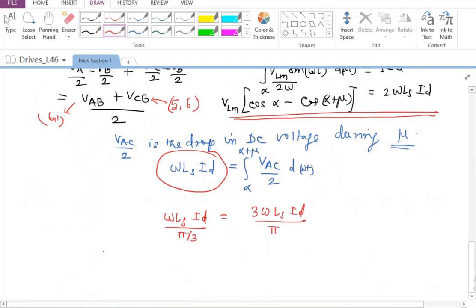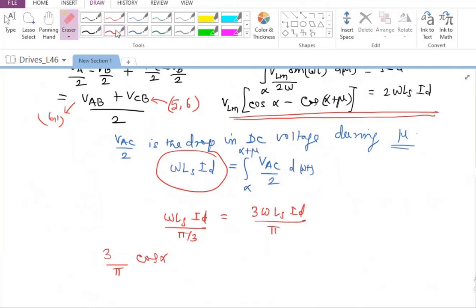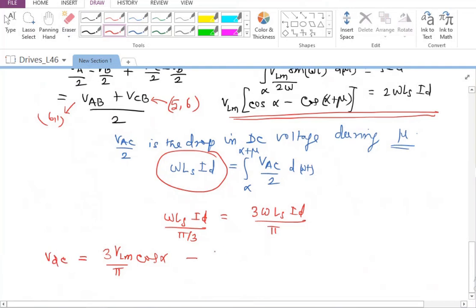So normally if we write 3 Vm divided by pi cos alpha, where Vm is the line voltage peak. Let me write this as VLM divided by pi cos alpha as the DC link voltage. Now from this I have to subtract 3 omega LS ID divided by pi, and that is going to be the DC link voltage. And if already this is negative, this will be adding to the total negative value. So the negative value would have increased as far as the DC voltage is concerned for an LCI.